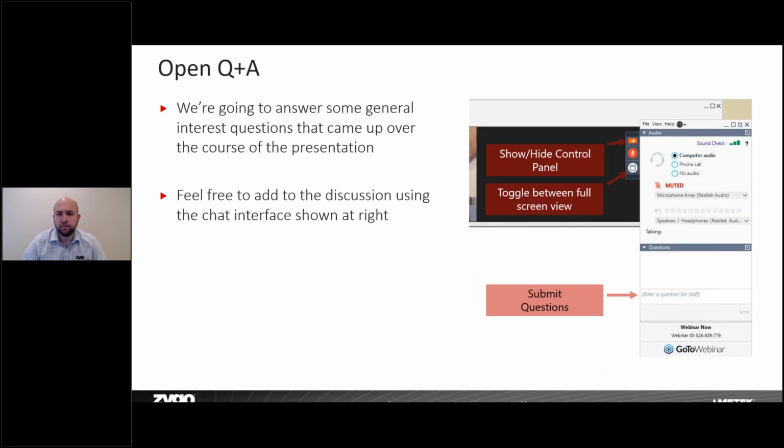Next question here. We talked about mirror coatings in this presentation, but can you measure thin film, especially two-dimensional thin film? You can measure thin films with the NewView. With the NewView, you're going to be able to measure films between generally 1 micron up to about 100 or so microns. If you need to go to thinner films than that, then the NexView is able to measure films down to about 50 nanometers.